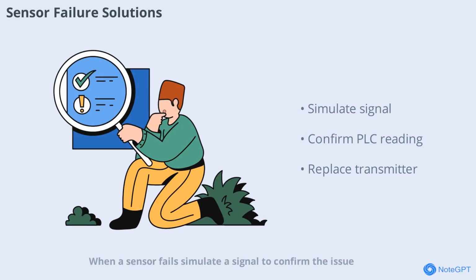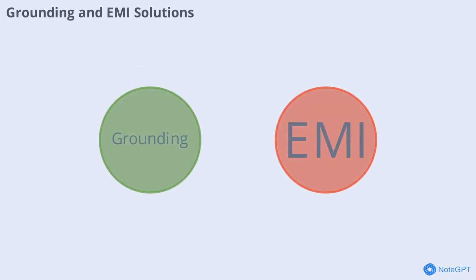When a sensor fails, simulate a signal to confirm the issue. If the PLC reads the simulator correctly, replace the faulty transmitter. This ensures that analog inputs remain accurate and responsive to process changes. Address grounding and EMI noise by ensuring shields are grounded at a single point and routing power cables away from signal cables. These steps prevent signal fluctuations and maintain system stability.